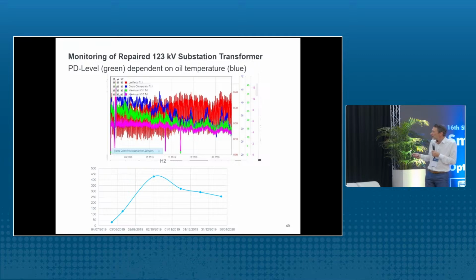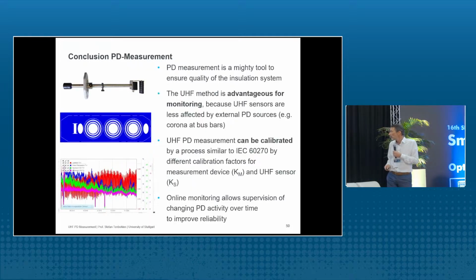The end of this story was, here is a longer time, so here we can see half a year of monitoring data, and in this case the green is the PD value, and you can see that the PD value is decreasing. In parallel there were also some DGAs measuring the hydrogen content, and also the hydrogen content is falling. There was a peak here, but then it is falling, and the transformer is still in operation, and PD was really reduced, maybe because the carbon particles are now somewhere in the region where no electrical field is, so moved away from the risky areas, so the transformer can operate.